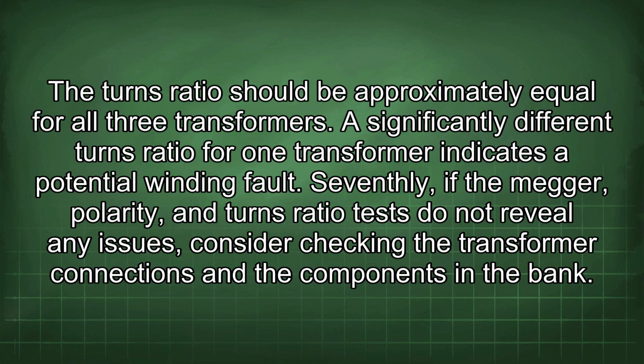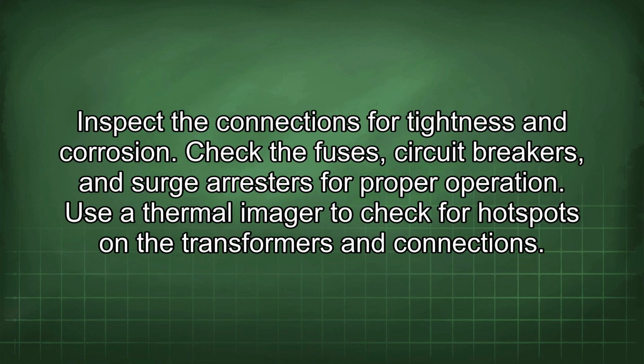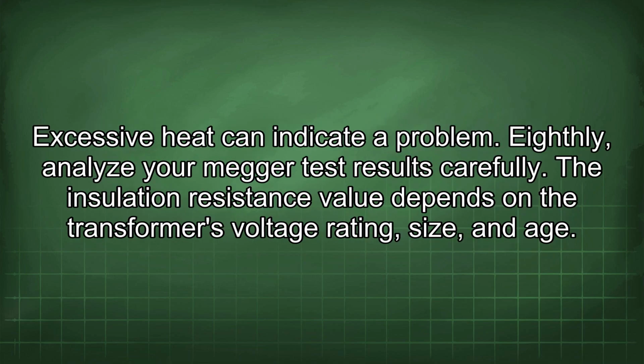Seventhly, if the megger, polarity, and turns ratio tests do not reveal any issues, consider checking the transformer connections and the components in the bank. Inspect the connections for tightness and corrosion. Check the fuses, circuit breakers, and surge arresters for proper operation. Use a thermal imager to check for hotspots on the transformers and connections. Excessive heat can indicate a problem.